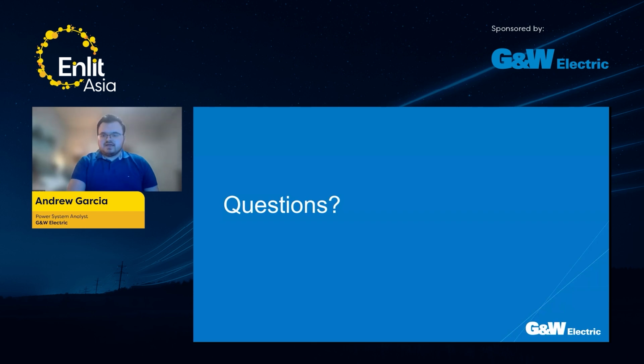What are the utilities' practices when they discover that the short circuit level is higher than the rated design? Based on your experiences, do they replace their equipment or consider current limiting devices as solutions? Traditionally, utilities have relied on going with higher rated equipment, but what we're seeing, once again, as the power grid revolution is happening, is that that's no longer entirely a practical solution, because the higher ratings they may need may not be readily available.